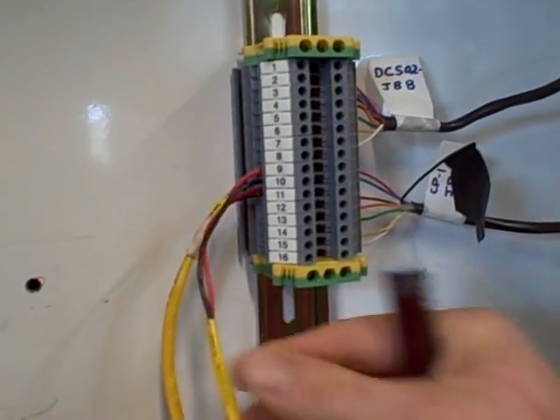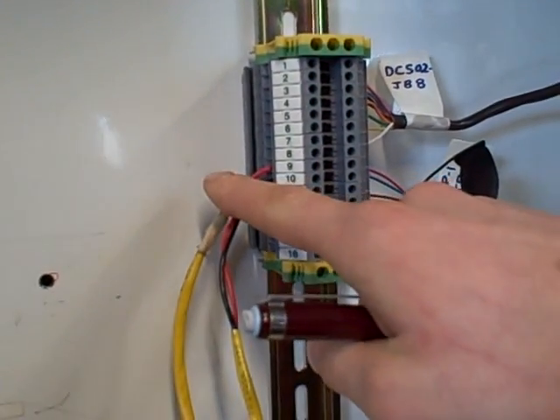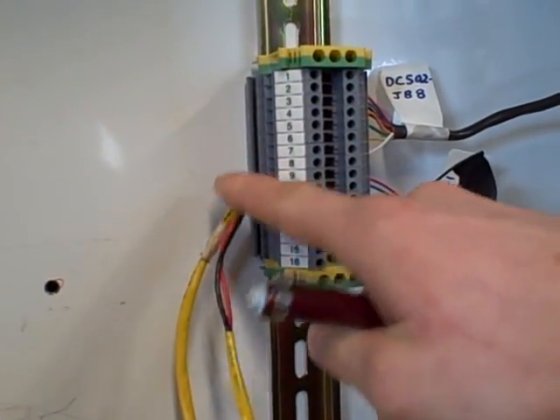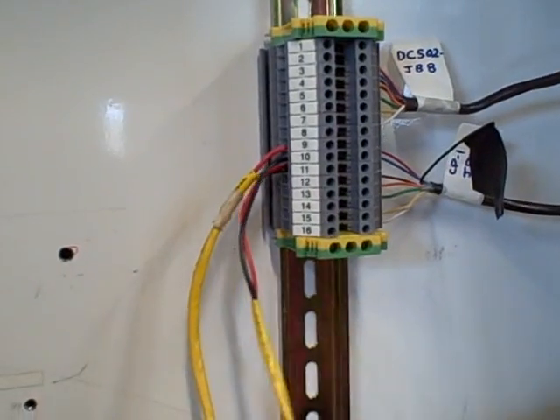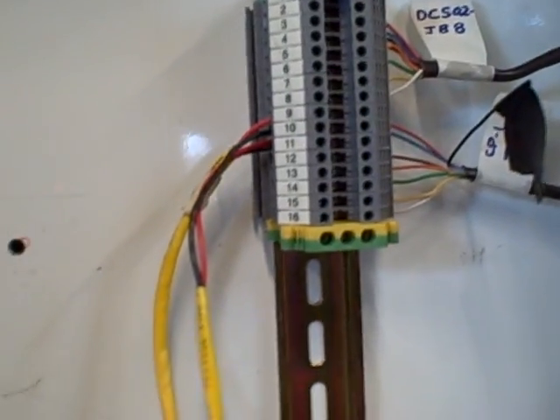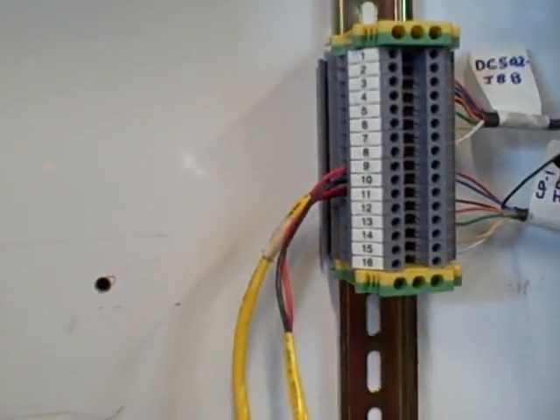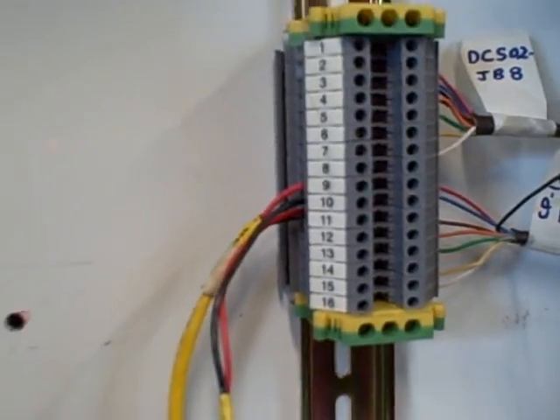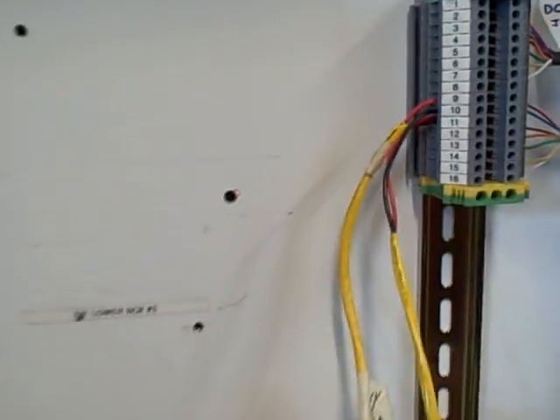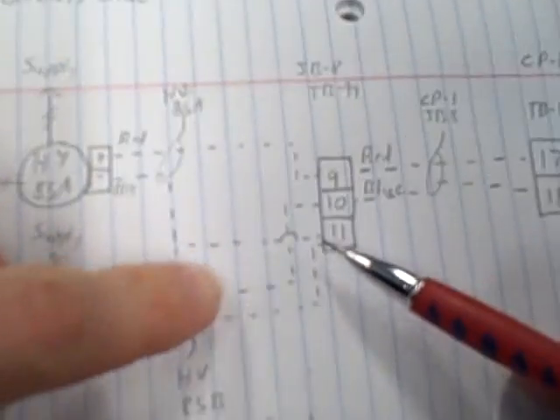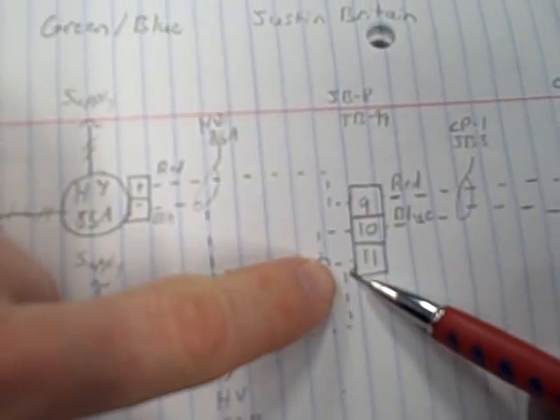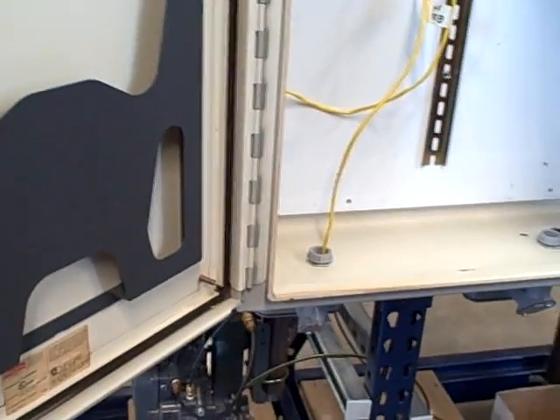Okay. So this cable is labeled HV85B, as you can see. And so this here would make the series connection from one valve to the other valve, and so now we'd be following the cable, HV85B. So it looks like terminal 11 is the common junction point between the two series cables. Is that correct? So for example, looking at this terminal 11 right there, that's the common junction point between that cable and that cable joining the terminal 11. Okay.